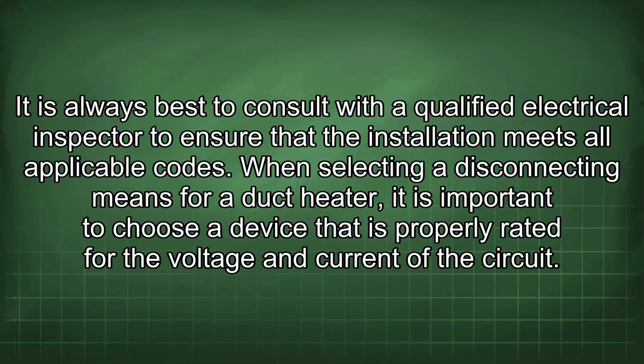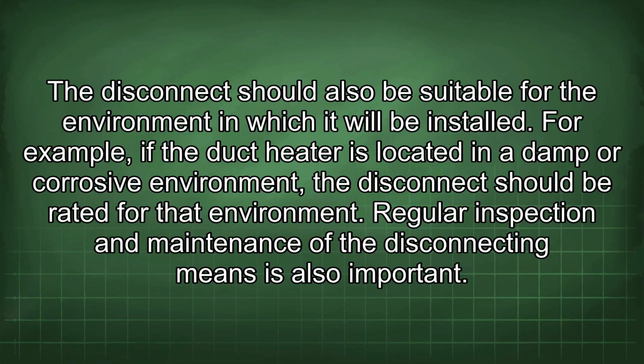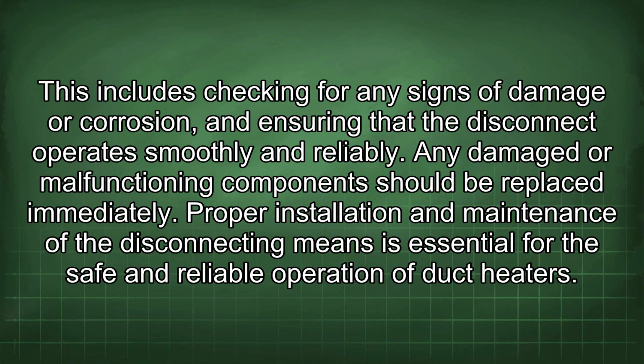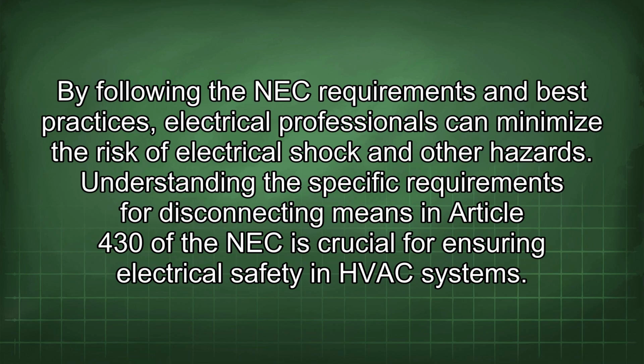When selecting a disconnecting means for a duct heater, it is important to choose a device that is properly rated for the voltage and current of the circuit. The disconnect should also be suitable for the environment in which it will be installed. For example, if the duct heater is located in a damp or corrosive environment, the disconnect should be rated for that environment. Regular inspection and maintenance of the disconnecting means is also important. This includes checking for any signs of damage or corrosion and ensuring that the disconnect operates smoothly and reliably. Any damaged or malfunctioning component should be replaced immediately. Proper installation and maintenance of the disconnecting means is essential for the safe and reliable operation of duct heaters. By following the NEC requirements and best practices, electrical professionals can minimize the risk of electrical shock and other hazards.